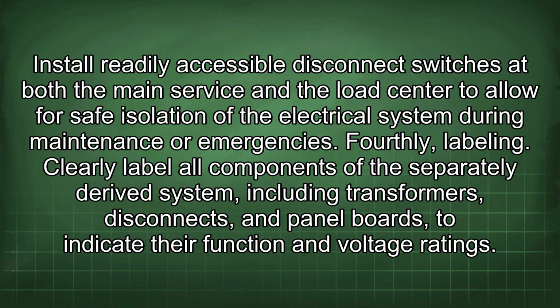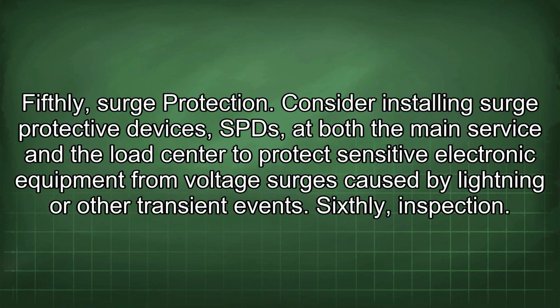Fourthly, labeling. Clearly label all components of the separately derived system, including transformers, disconnects, and panel boards to indicate their function and voltage ratings. Fifthly, surge protection. Consider installing surge protective devices, SPDs, at both the main service and the load center to protect sensitive electronic equipment from voltage surges caused by lightning or other transient events.